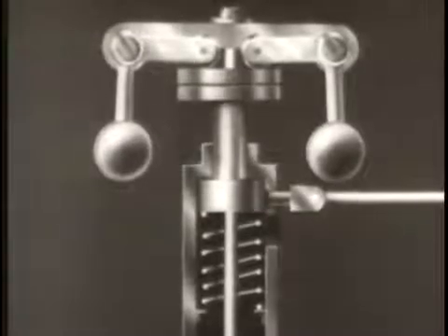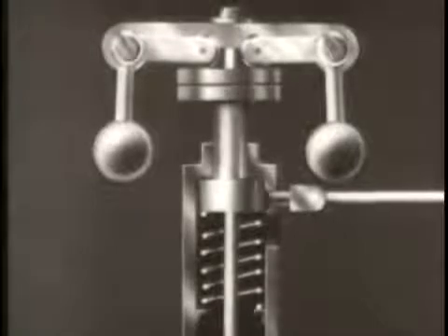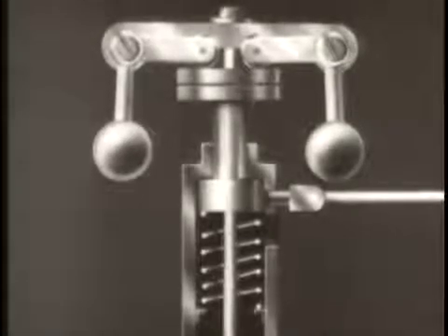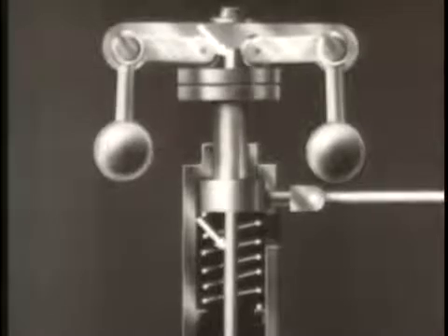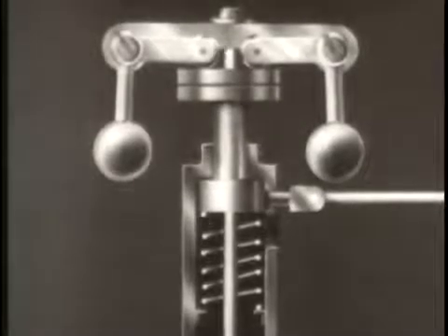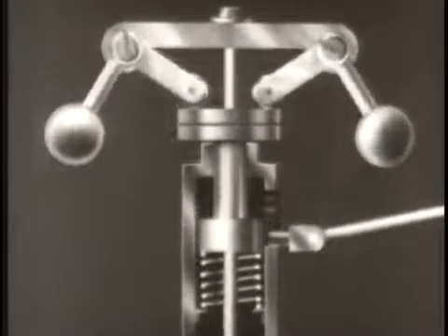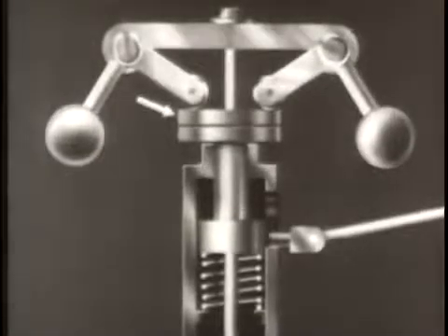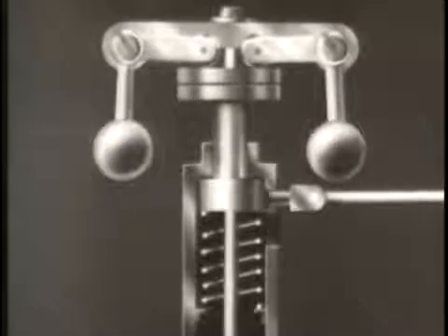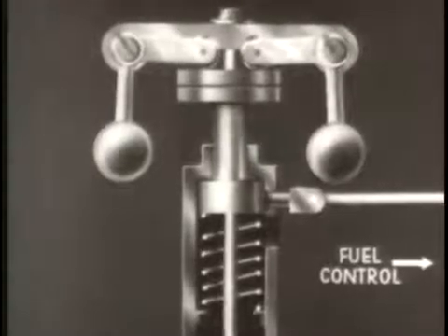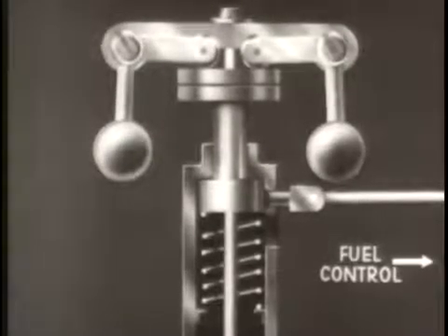One type of governor is the overspeed governor. It acts merely as a safety device and keeps the engine from overspeeding or racing. The basis of the overspeed governor is a pair of flyweights mounted on the drive shaft. The outward motion of the flyweights is transmitted to a collar which slides on the shaft. The movement of this collar actuates a linkage to the fuel pump controls.